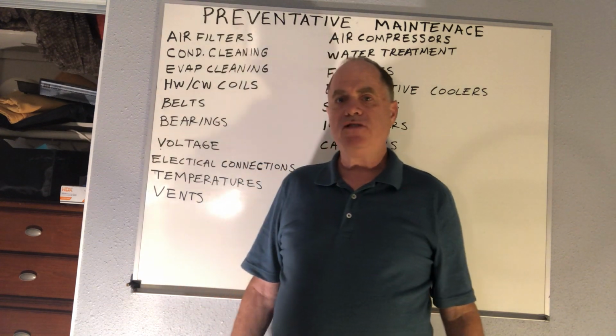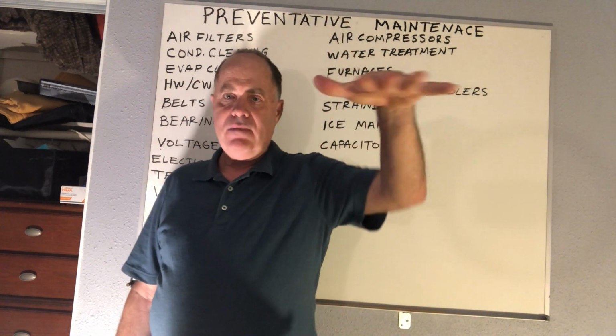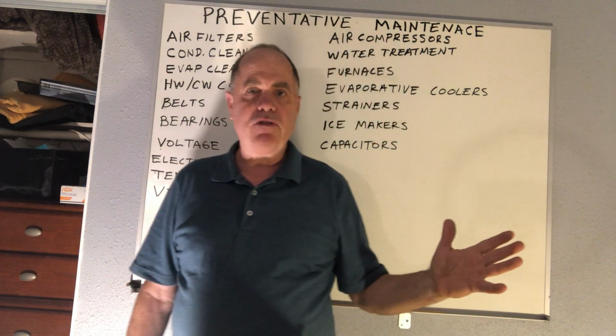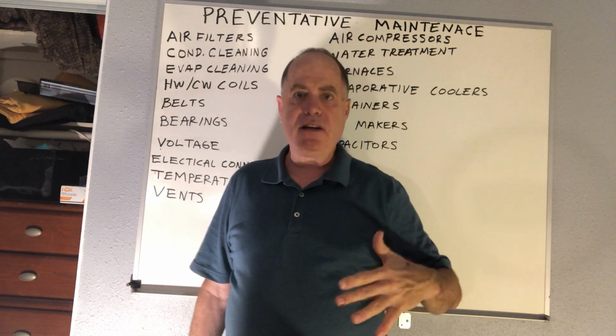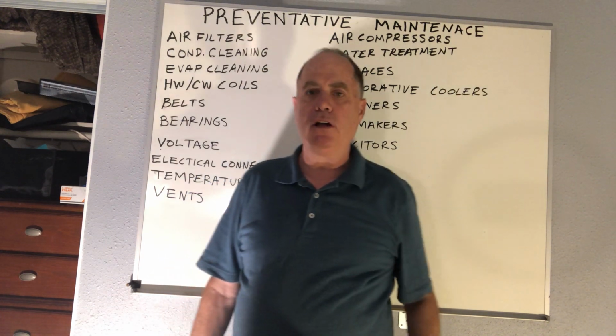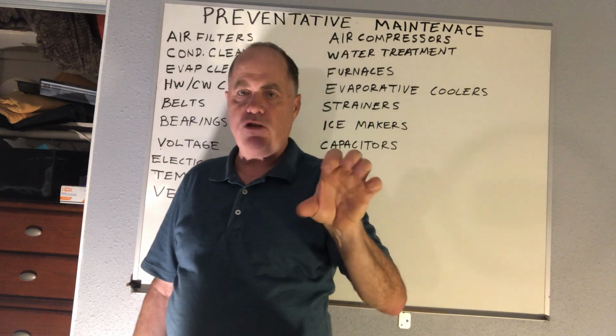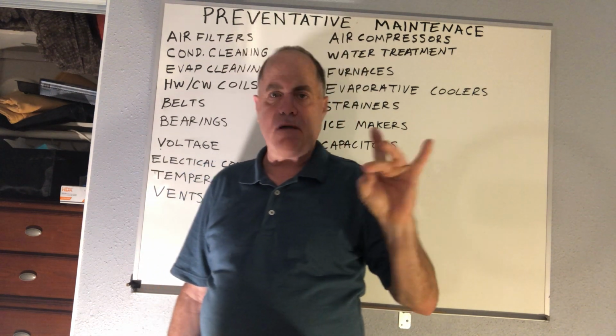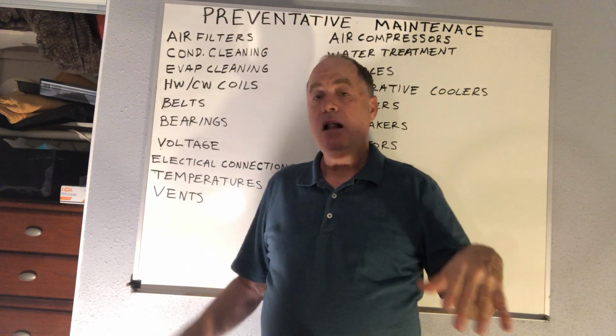You know, a lot of times just doing that for air conditioning, making sure you feel a little warmth coming off your condenser, letting it run for a number of minutes and seeing that temperature drop, feeling that you have good airflow, that also can verify that your charge is okay. It's not necessary to be hooking up the gauges on maintenance very often, okay?